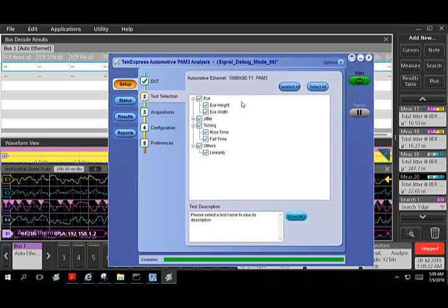So in this case, these are all different measurements we support for the signal separation. One of the very important things to note here is the voltage level of the separated signal. Unlike a directional coupler, here you get approximately 900 millivolts to 1000 millivolts of peak-to-peak signal for both master as well as slave signal. So next step, we are going to perform some of the analysis for the master as well as the slave signal, and we support eye diagram, the jitter measurements like the total jitter, rise time, fall time, and the linearity measurements.